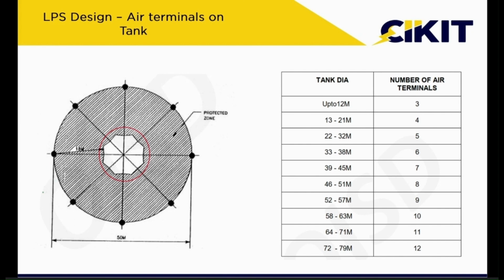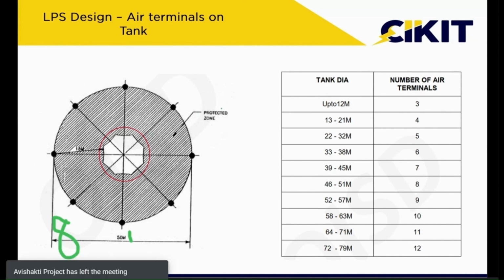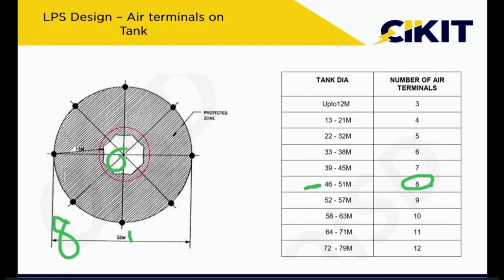Here, if you observe, the diameter is 50 meters and the air terminals are 1, 2, 3, 4, 5, 6, 7, 8. So there are 8 air terminals placed along the perimeter of this particular tank. They have already performed this calculation and provided the number of air terminals required for different tank diameters. If you take this particular category, this one comes under 46 to 51 meters. So for 46 to 51 meters, we require 8 air terminals. We have checked here also, and here also we have placed around 8 air terminals. But the drawback of this particular method is that the center portion becomes unprotected. This area is not protected by using this particular method.